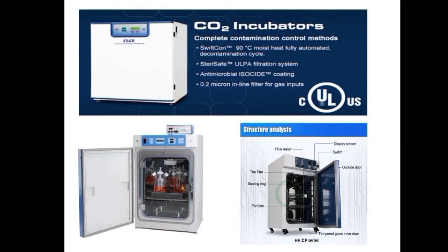Second one is the incubators, or you can call them the gas incubators. Inside the CO2 incubators, an atmosphere is created that is as natural as possible to develop cell and tissue culture. This way of cultivating living organisms is called in vitro, and it is the main application of the CO2 incubators.